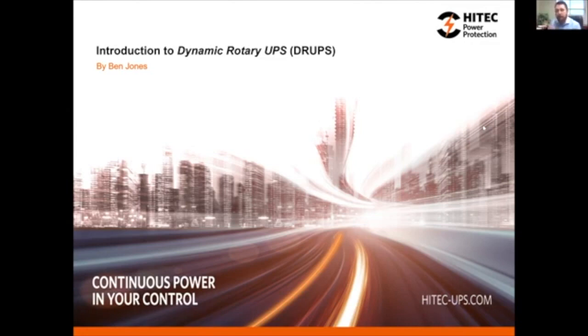UL, no, UL 2200 I think I heard you say, that's specific for diesel generators. We have our own UL code, but there's no UL stamp. Part of our offer is to get the system UL verified. The difference between certified and verified is that as part of our scope, we hire a third party to come in and rubber stamp it. Then you have a UL system, but you won't get the UL stamp itself, it's not a component stamp, so it doesn't mean anything different for you. You still meet your UL requirements.